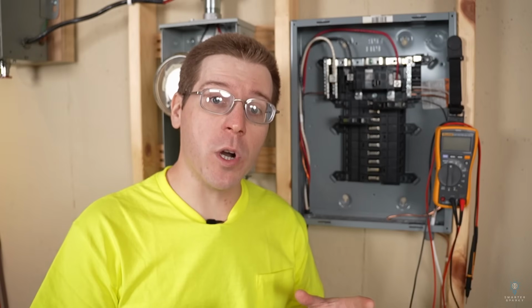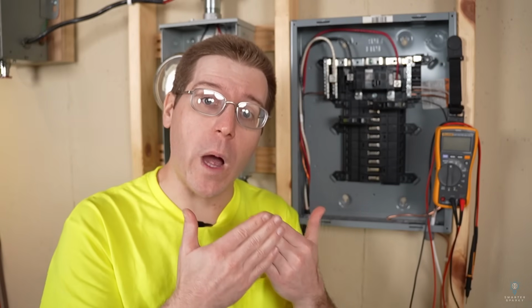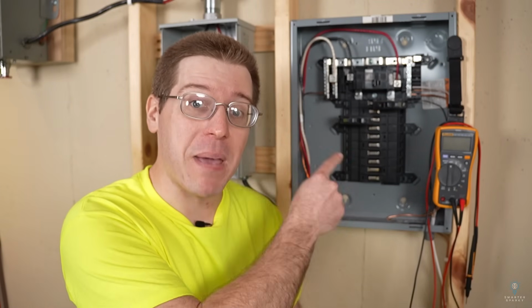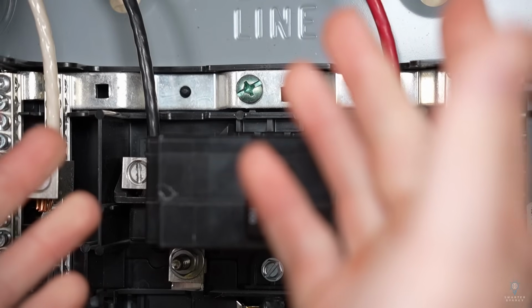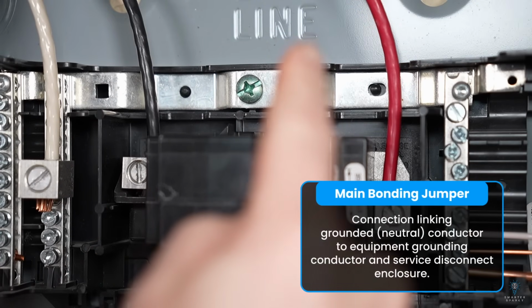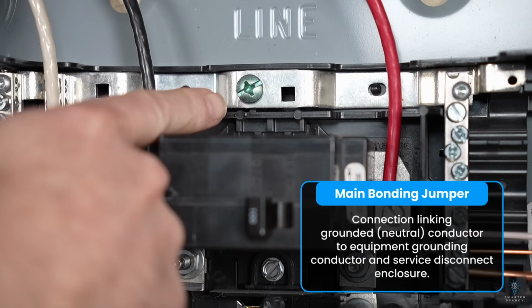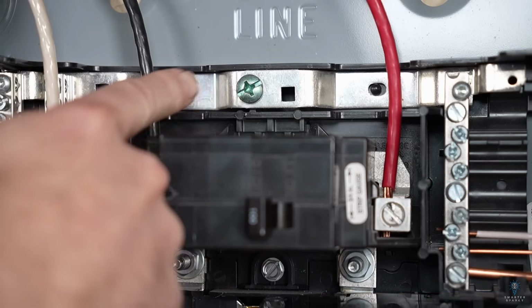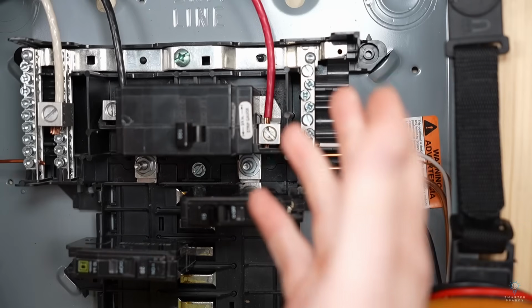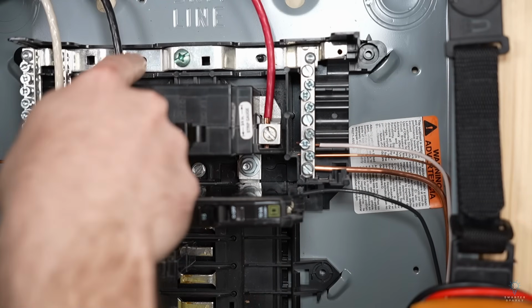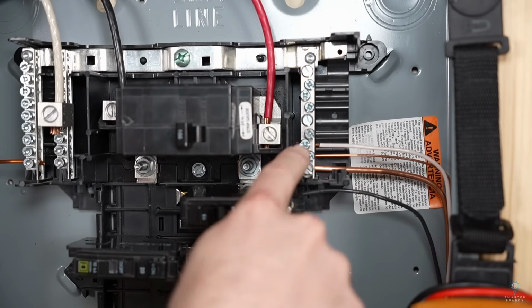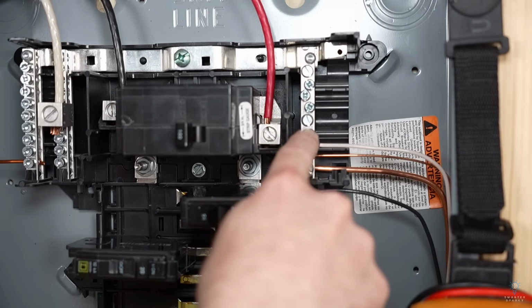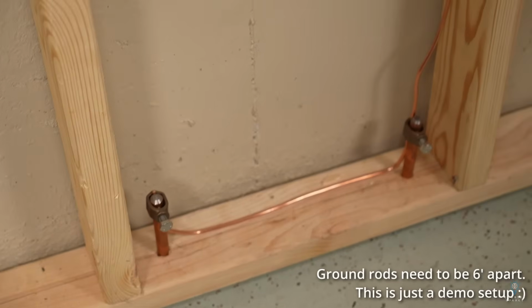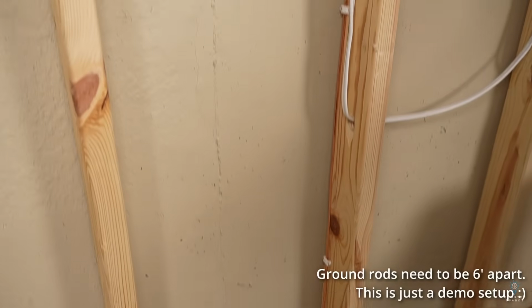In order for that to work, ground and neutral are required to be connected together in the main panel. The point at which this happens is called the main bonding jumper. And in most residential panels, it's this green screw bonding the neutral bar to the metal enclosure. Because grounds and neutrals are required to be connected together anyway, they're allowed to terminate on the same point in the panel. The ground rods are simply a reference to Earth.